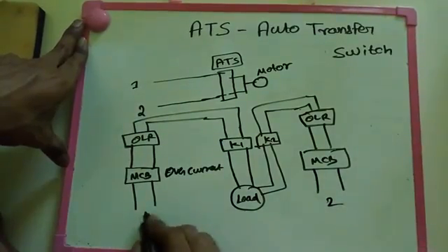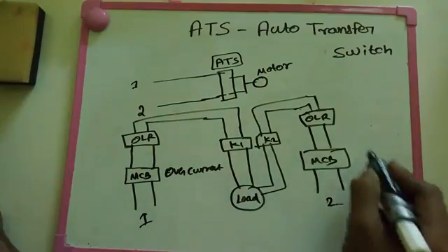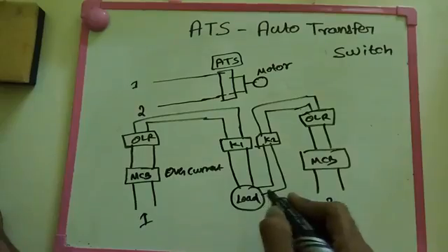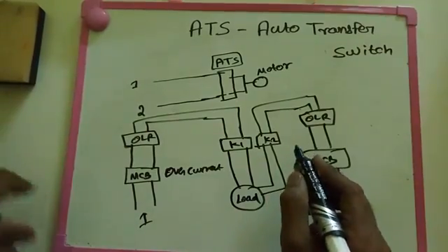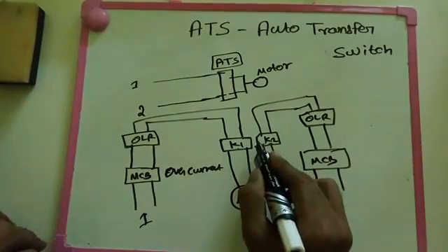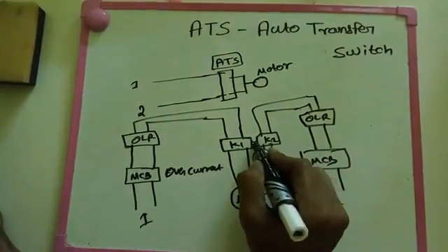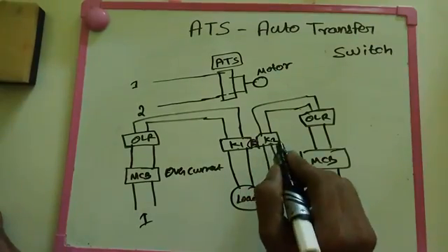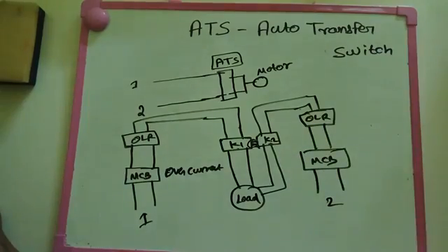And then supply 2 - this one is supply 1. So this is how a single load is connected to two supplies, giving continuous supply to the load. Now I'll show you some control circuit on how we control this full system. The K1 and K2 are the main contactors. These two contactors are mechanically interlocked or electrically interlocked - whatever you need for your convenience. We need to make this interlock so that only one supply will be operated at a time, not both.